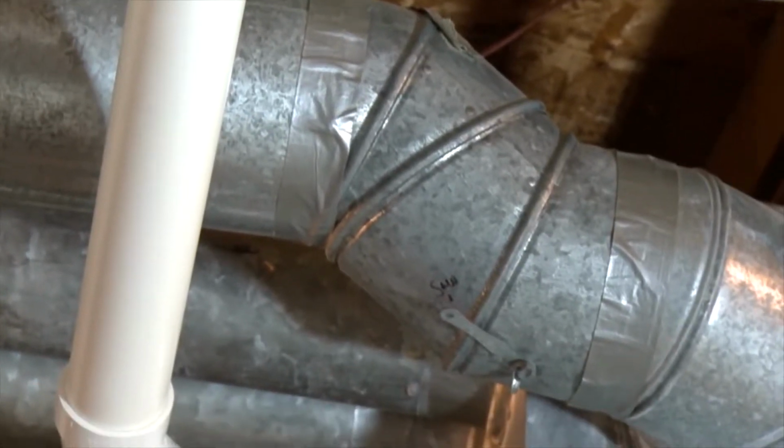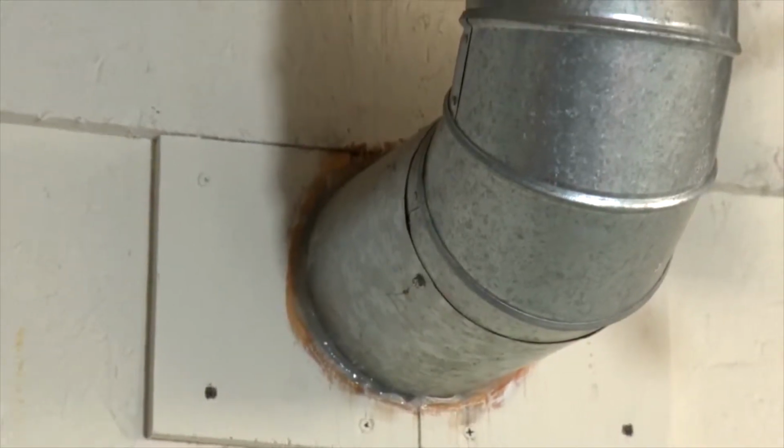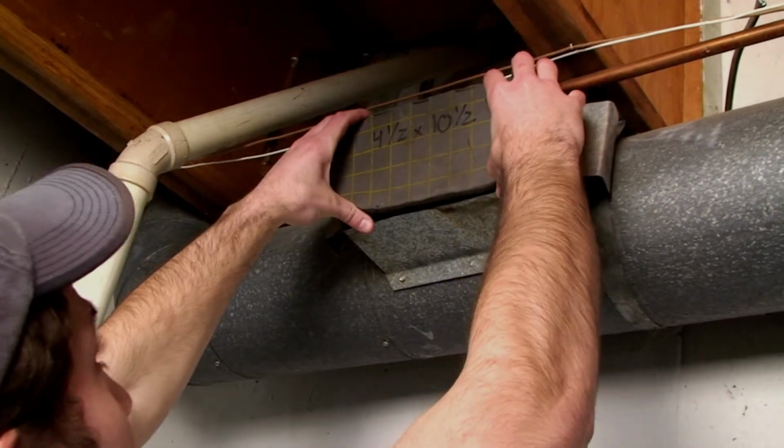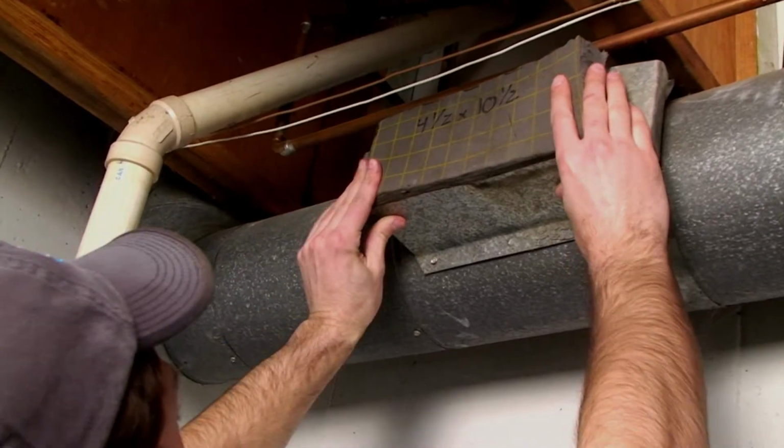I tried using all the conventional methods to correct the problem. I tried to use duct tape, caulking, especially on all the ductwork that I could see in the basement. But all of this was ineffective because the air leak itself was actually coming through the walls and not the ductwork. First, a technician will install foam plugs into all air duct openings.